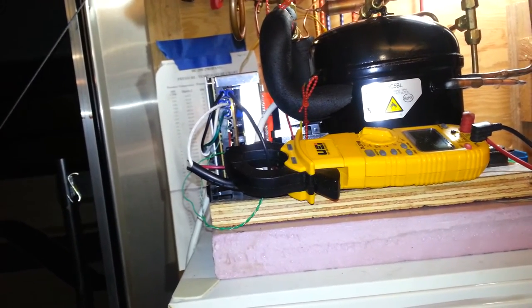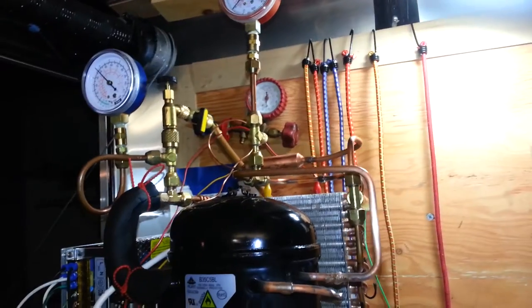negative 10, negative five, which is much, much cooler than it needs to be. So it's increasing that compressor compression ratio higher than I'm comfortable with.